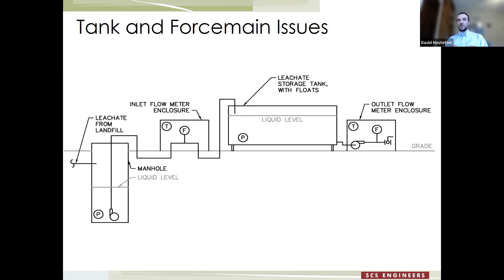So after the flow meters were installed, we were monitoring the amount of liquid that was being taken on an instantaneous basis through that inlet flow meter, and it was right around 100 gallons per minute for several months. And then we saw the flow really start to drop off very steadily over time. So it was 100, 98, 99, 97, just kept on going down, eventually got down to about 80 gallons per minute. And we're like, okay, this isn't some sort of temporary thing. Something's up with this. We need to go out there and check it out. So Diane will flip to the next slide here.